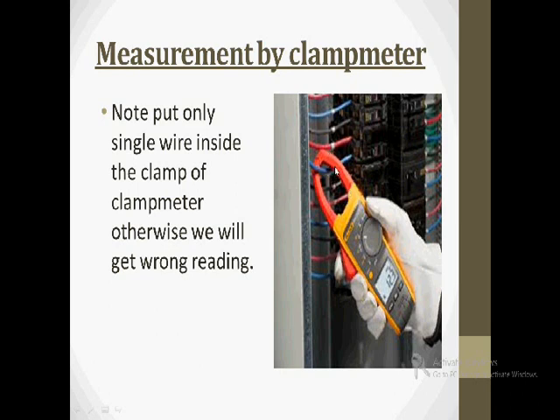Always put one wire. And keep one more thing in mind that while checking the current of one wire, your clamp meter must not touch to the other wire. Otherwise, you will get the wrong reading.